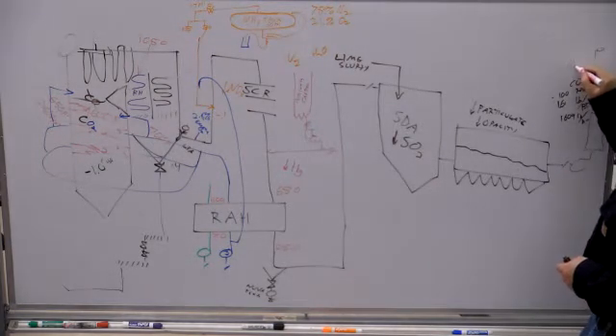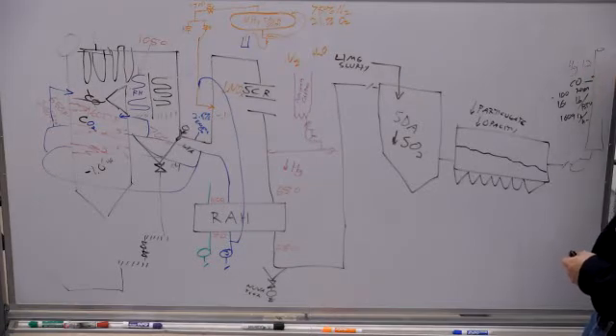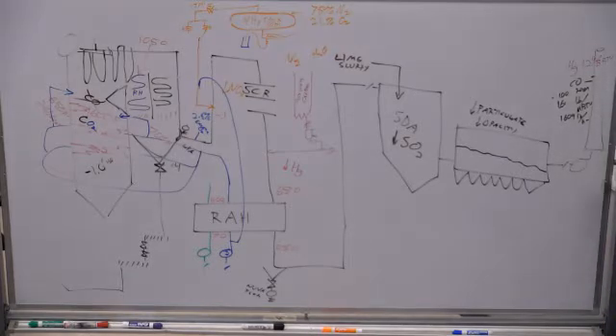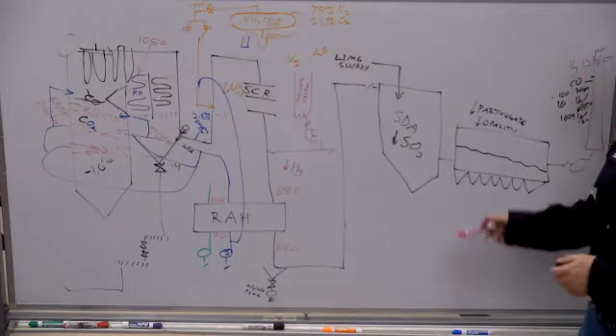So mercury, 1.2 pounds per billion BTU. And over here it was a million BTU. So 1,000th as much. The limit is way tiny. And we normally run at 1.0 with that limit of 1.2.